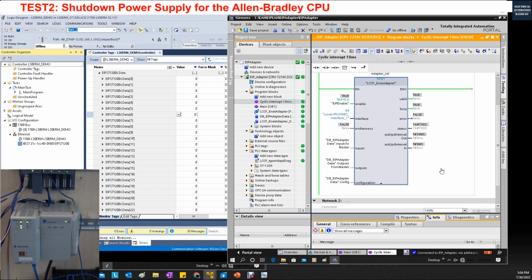So now we can see, after the Allen-Bradley controller boots up and after a couple of seconds, we saw this I/O indicator flickering. After that, we'll see on the right side this violet shows on. That communication automatically recovered. This is really great.